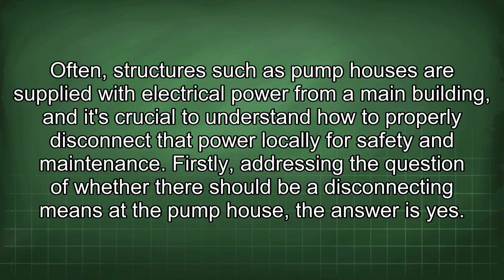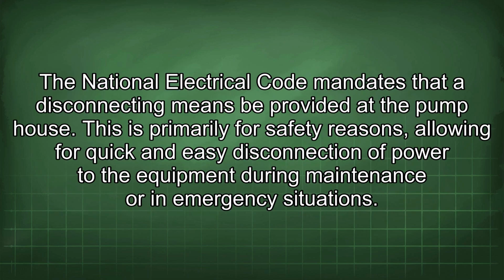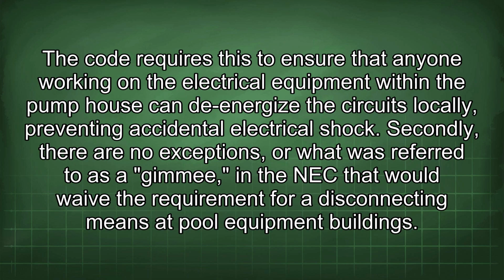Firstly, addressing the question of whether there should be a disconnecting means at the pump house, the answer is yes. The National Electrical Code mandates that a disconnecting means be provided at the pump house. This is primarily for safety reasons, allowing for quick and easy disconnection of power to the equipment during maintenance or in emergency situations. The code requires this to ensure that anyone working on the electrical equipment within the pump house can de-energize the circuits locally, preventing accidental electrical shock.